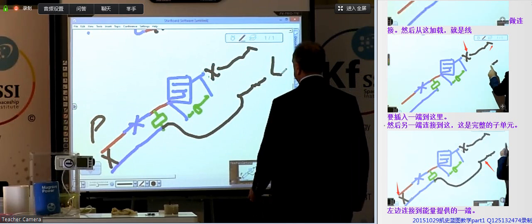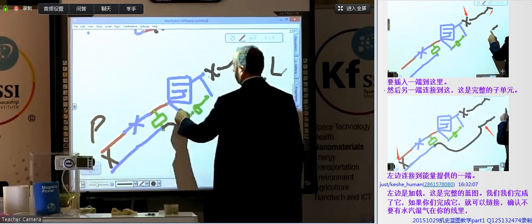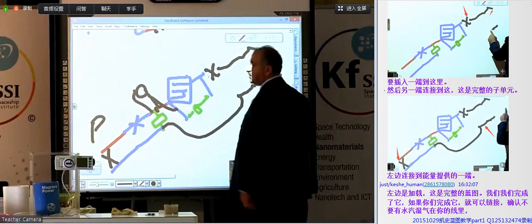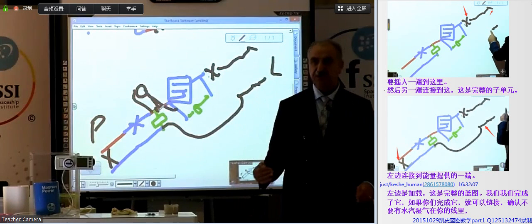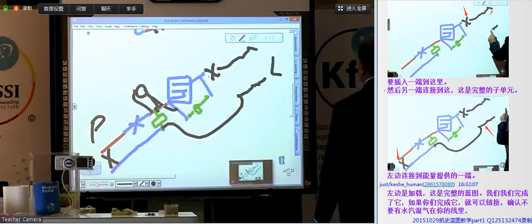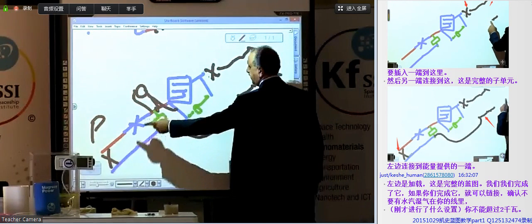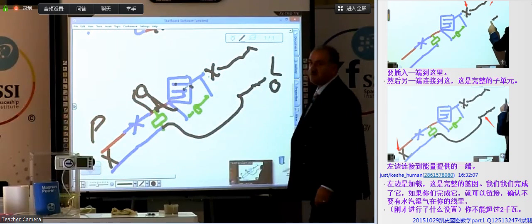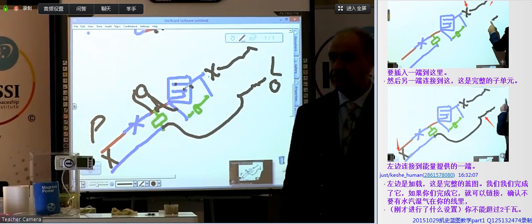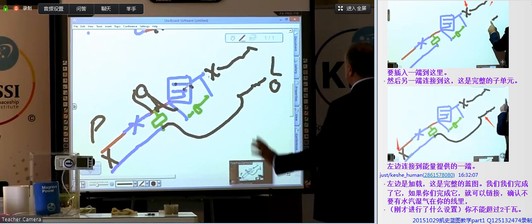What we've done, we have added a thermometer measurement system somewhere here, where if the wire gets heated, you get breaking of the circuit. Which means you cannot pass 2 kilowatts. So you have a safety that if you overload on this side, the line heating up your coil will disconnect you from the main. You cannot damage the system. It's set at 55 to 60 degrees. You need to put a thermometer at this point. This is what you have in the blue box.